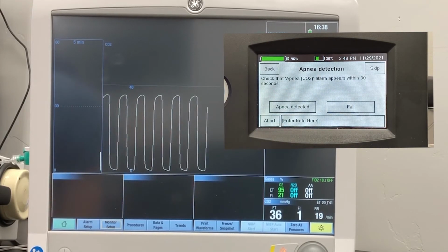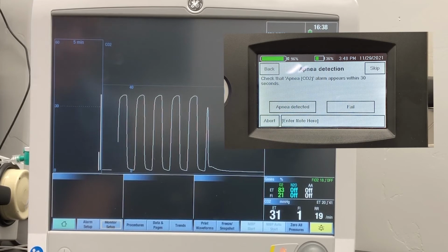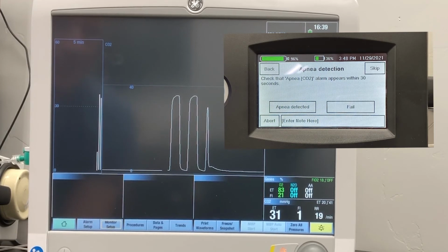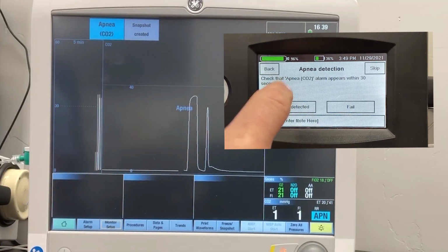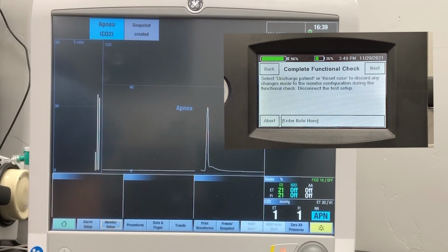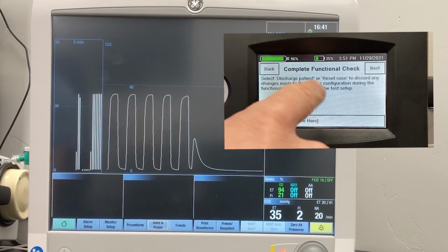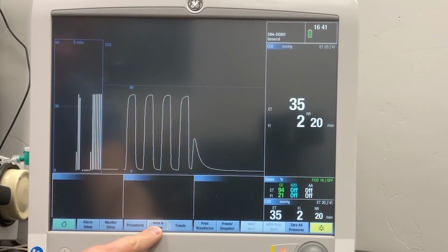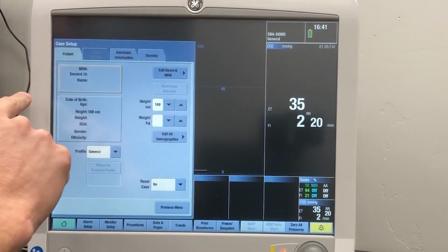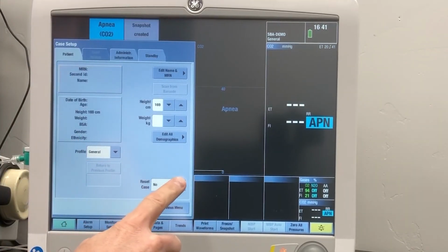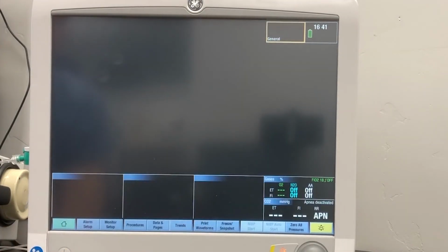Now that we hit pass on that last screen, it stopped simulating breath, so we should see an apnea alarm here shortly on the monitor. This allows us to verify the apnea alarm is working. There it is. So apnea detected. It's a passing result. So next, to complete the test, we've got to discharge or reset the case. So we do that by touching data and pages, start reset case. Down here under reset case, we set that to yes, and it'll reset the monitor.